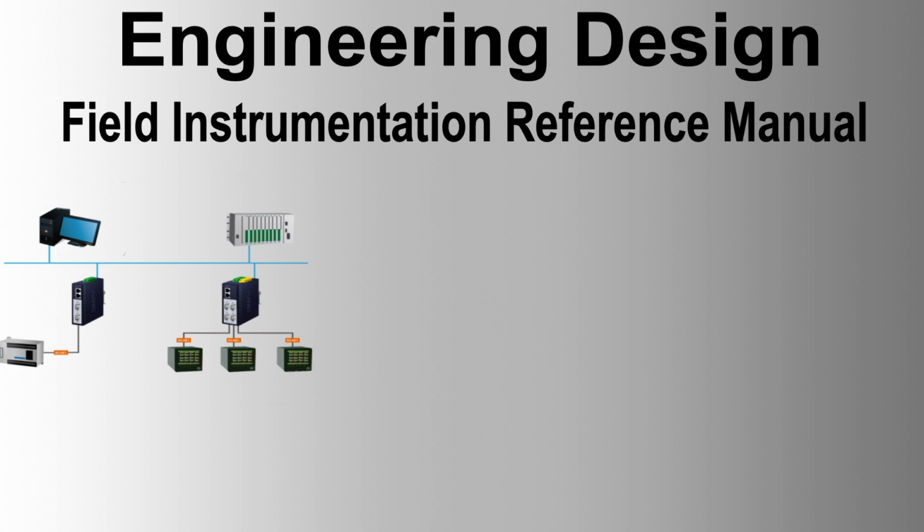Location and accessibility. Field-mounted instruments shall be installed considering their location and accessibility, avoiding excessive vibration and ensuring representative measurements. Limited accessibility is acceptable for indicating instruments if they can be properly read from a permanently accessible location. Heavy equipment should be accessible by mobile hoisting equipment or have permanent hoisting facilities if necessary. Instruments and their impulse lines should have sufficient free space for maintenance activities.